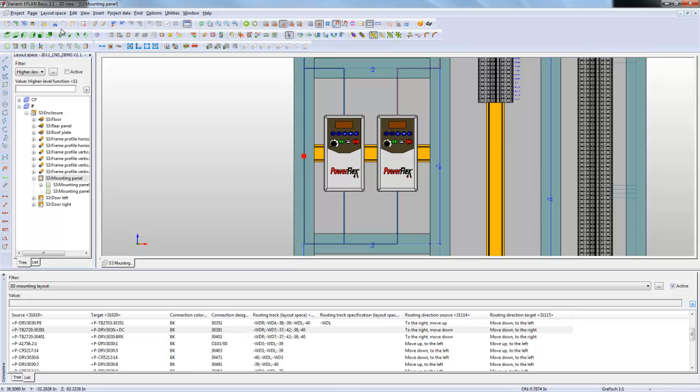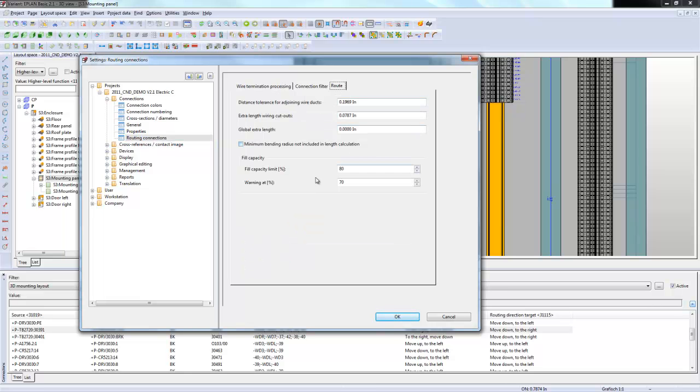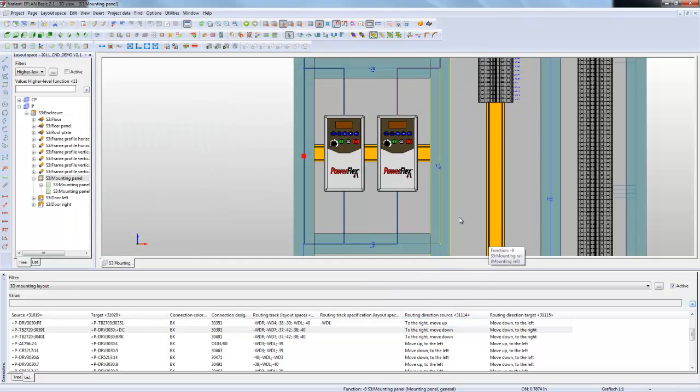What you have here under the wrench, you have the routing connection. These are options for the project. You have a routing tab and you can specify the fill capacity to give you a warning at 70% or a fill capacity limit of 80%. You can always play around with these and say I want my wire ducts to have some more space or less space, a little bit more breathing space and stuff like that. You can set all that up. That's pretty much in a nutshell how that works out.